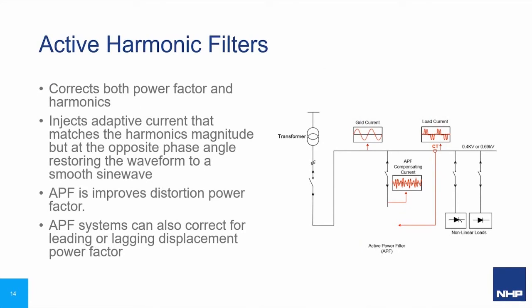They can correct both power factor and harmonics. The way that they work is that they inject adaptive current that matches the harmonic magnitude, but at the opposite phase angle, restoring the waveform to a smooth sine wave. So by mitigating harmonics, the APF is improving the distortion power factor on site. APF systems can also correct for leading or lagging displacement power factor, same as SVG.